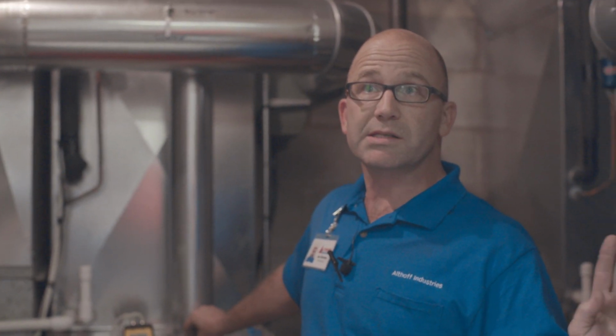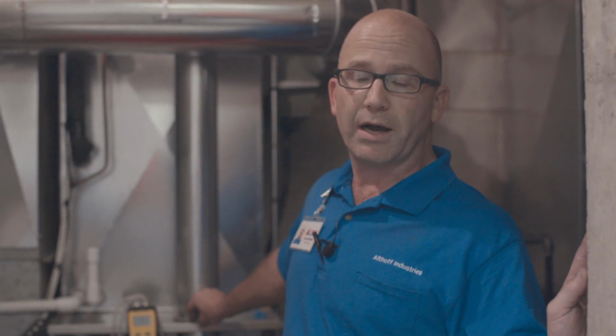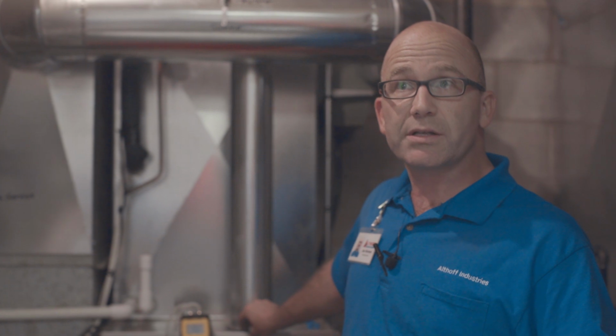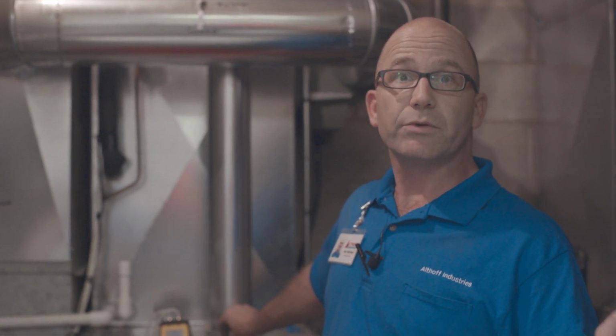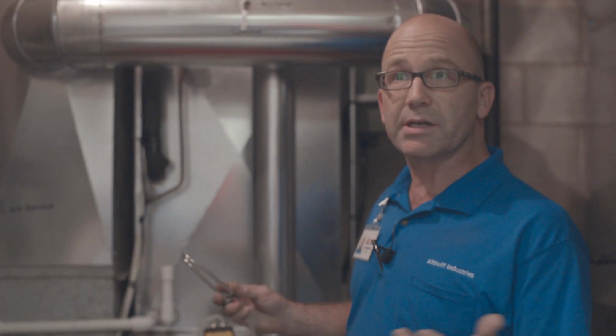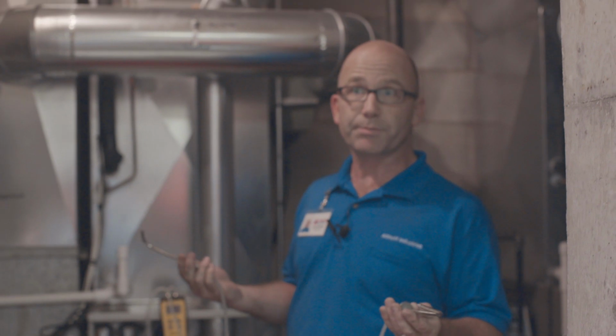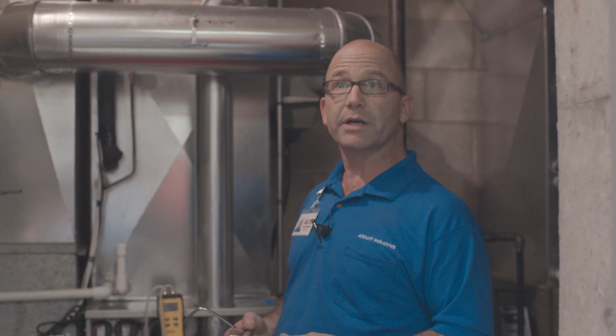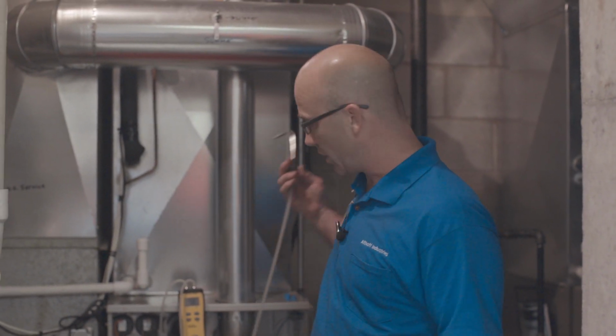The experts tell us 75% of all air furnace and air conditioning problems are airflow related. So that's the reason we check it. Every clean and check that gets done and every problem call that gets done, we check static pressure, meaning airflow. This is an example of how we check it. We check it with a manometer, and these are static pressure tips. So we put these in the ductwork. Like I said, the higher the number, the worse off we are, right?